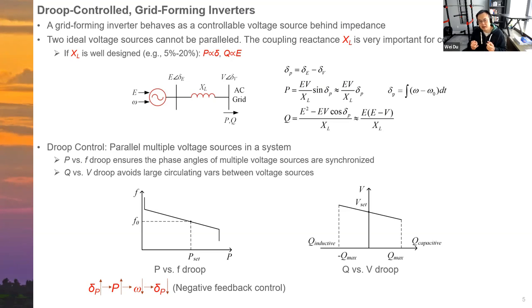However, there are two key elements for these grid forming inverters. Other than this voltage source, another important piece is the coupling reactance, because this reactance XL actually plays a major role in decoupling P and Q control. You can see in this slide, if this XL is well designed, P is approximately linear with the phase angle and Q is approximately linear with the voltage magnitude. So with this decoupling characteristic, people can design controllers to regulate P and Q by controlling the voltage magnitude and the phase angle.